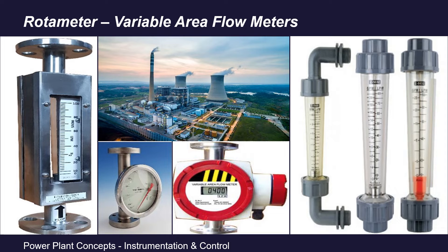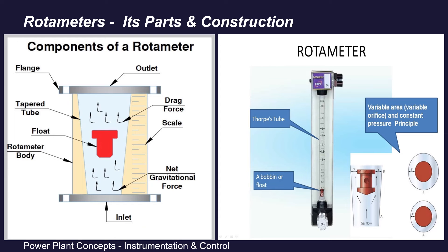Our first and foremost question is: what is a rotameter? We can say a rotameter is a variable area flow meter because in this meter the area of fluid flowing is varying as the float moves up or down in a tapered tube. It measures volumetric flow of liquid or gas. It is a reliable, simple, and low-cost flow measuring instrument. Sometimes these rotameters are also called gravity flow meters, mechanical flow meters, or variable area flow meters.